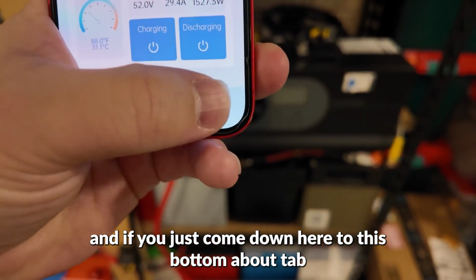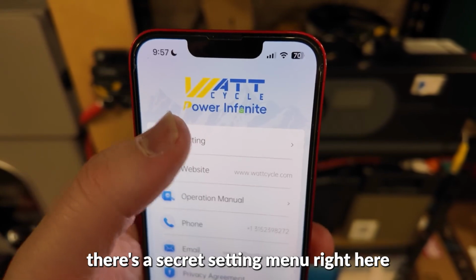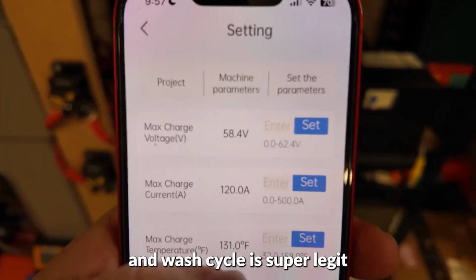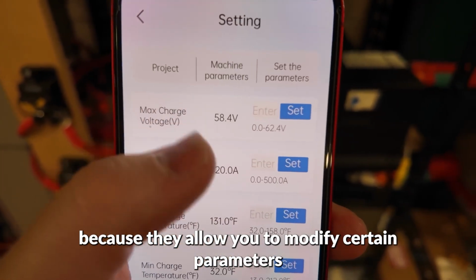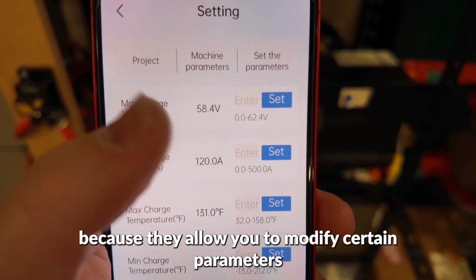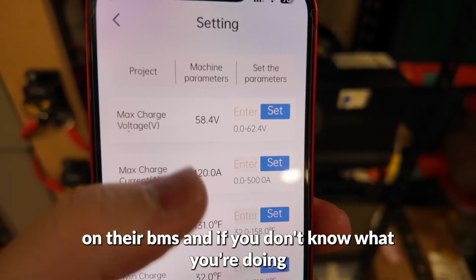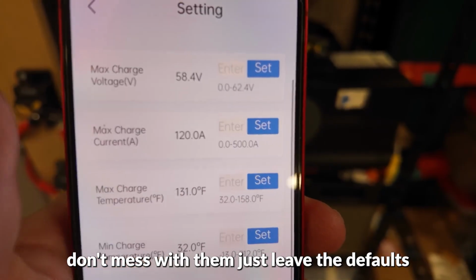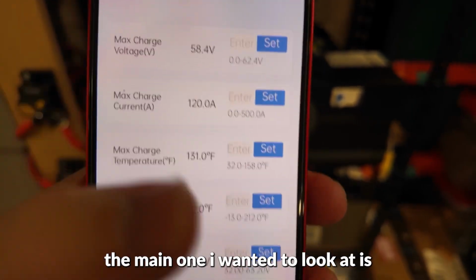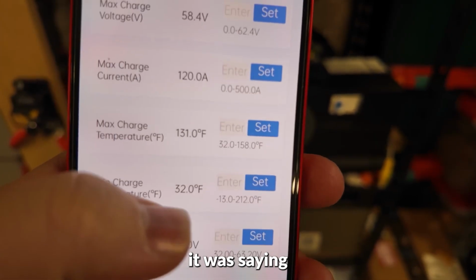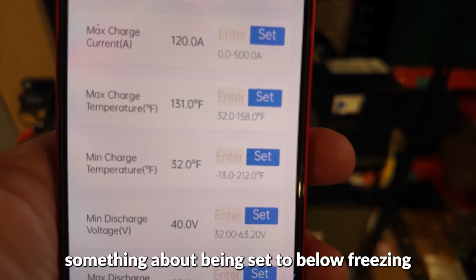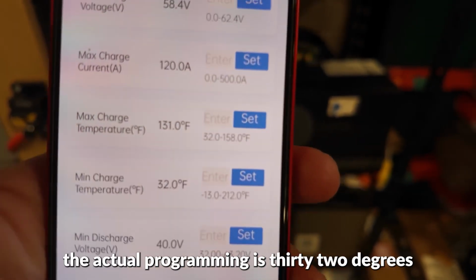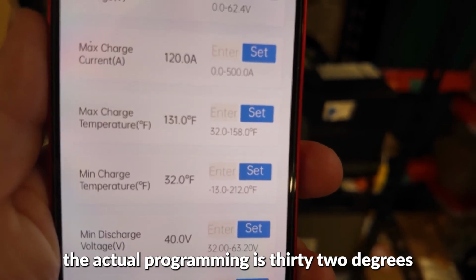It's pretty sweet. And then if you come down to this bottom About tab, there's a secret settings menu right here. WattCycle is super legit because they allow you to modify certain parameters on their BMS. If you don't know what you're doing, don't mess with them, just leave the defaults, and the defaults are pretty good. The main one I wanted to look at is, remember how in the manual it was saying something about being set to below freezing? Well, we can see right here the actual programming is 32 degrees.